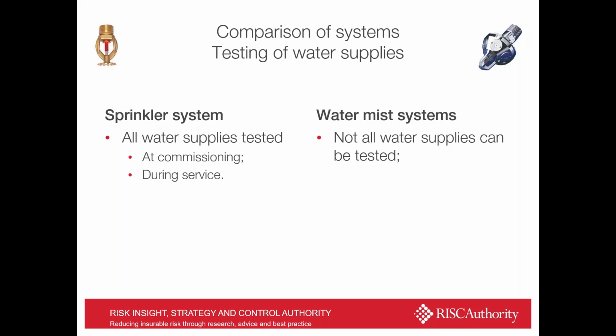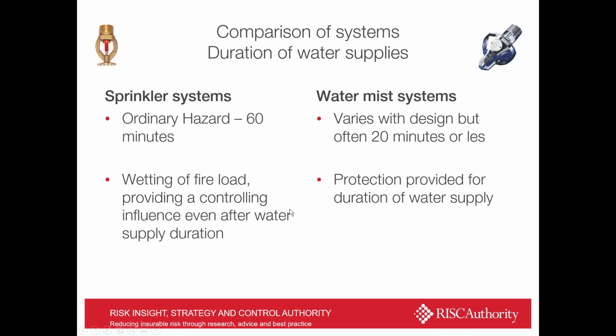Testing of water supplies is also a difference. Sprinkler systems are designed so that we can test the water supplies, and they are tested regularly, and with water mist systems, we find sometimes that's just not possible. Duration of water supplies: obviously, for a sprinkler system, it's defined by the hazard, but 60 minutes, 90 minutes, and even 120 minutes are not out of the question. And even after that water gets exhausted, were it ever to, the amount of water that's gone down can still have a controlling effect on the fire.